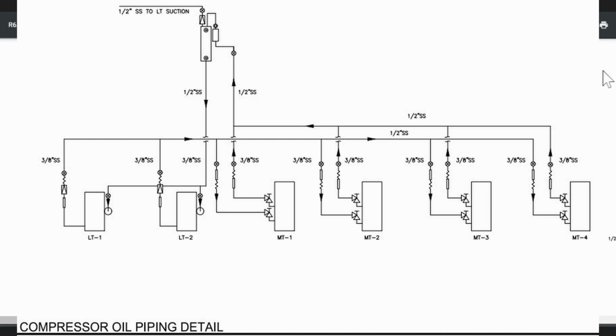Gets pumped out of the compressors into the evaporators. And so it's not very much oil when we open that little valve up. There's 4 heat exchangers, and the first 2 in line on the liquid line get all of the oil. The last 2 get very little. So we're talking about moving 3 or 4 ounces of oil out of the evaporators, the thermal siphon evaporators, or CO2 condensers, whatever you want to call them. Yeah. Back into the oil reservoir.